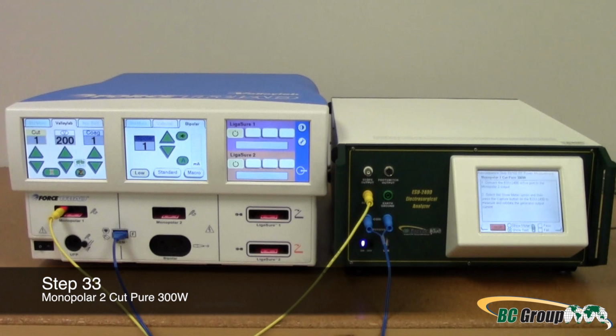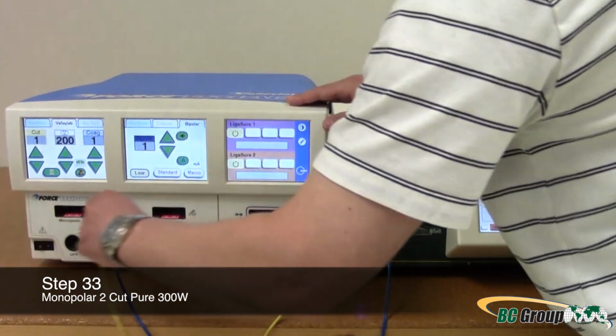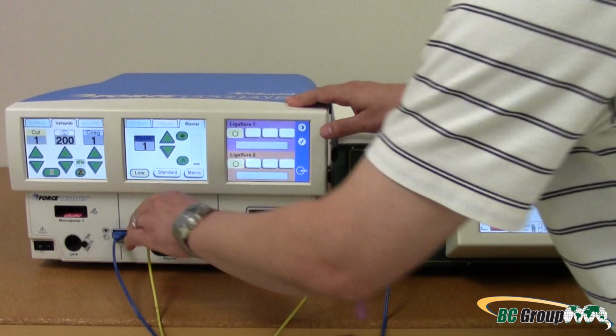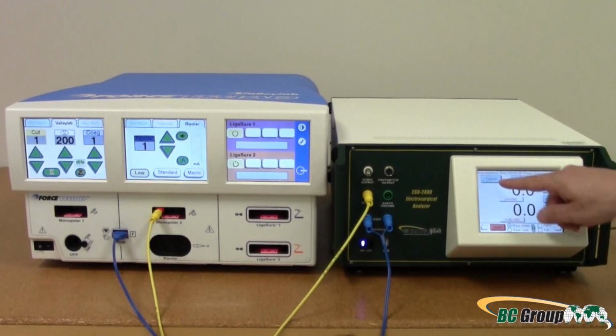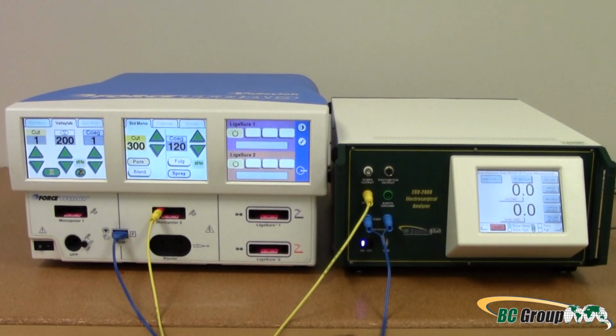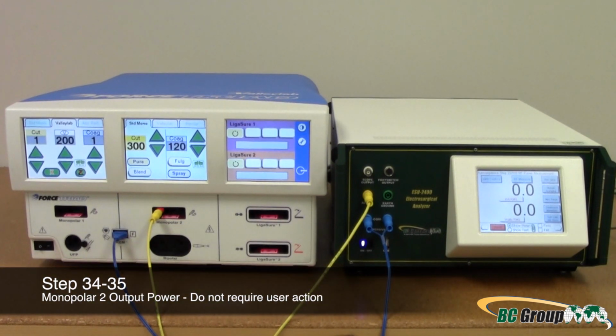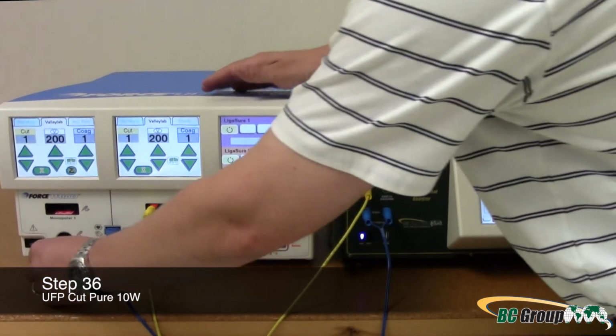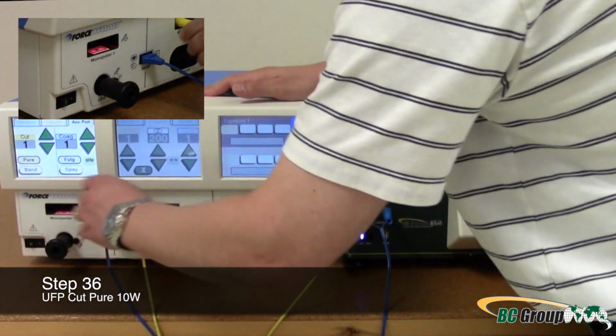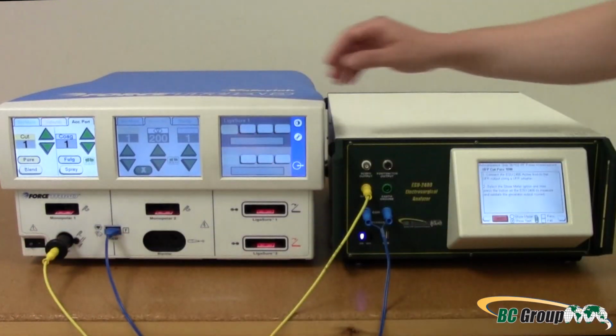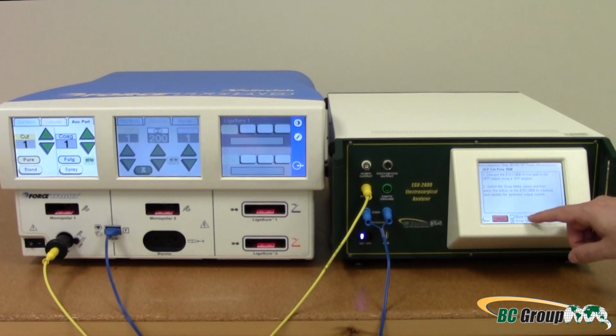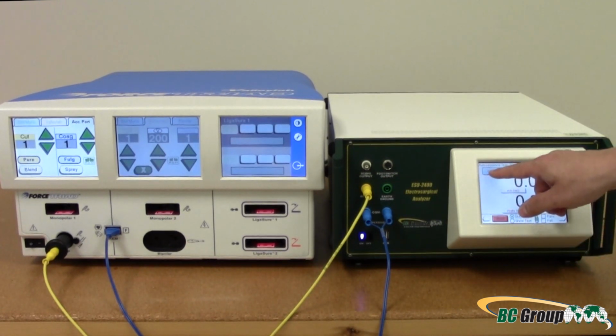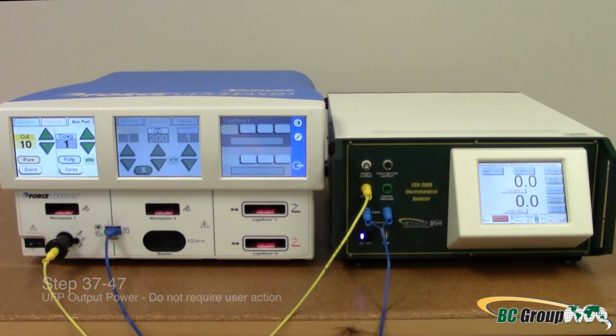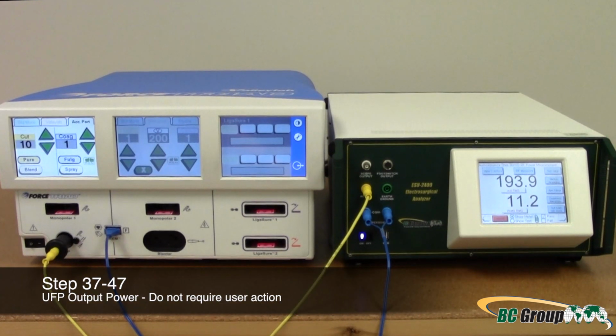Step 33. Monopolar 2, cut, pure 300 watt. Move the active lead from monopolar 1 to monopolar 2. Select Show Meter and then press Capture. Steps 34 through 35 do not require user action. Step 36. UFP cut, pure 10 watt. Connect the ESU-2400 active lead to the UFP output using the UFP adapter. Select Show Meter and then press Capture. Steps 37 through 47 do not require user action.